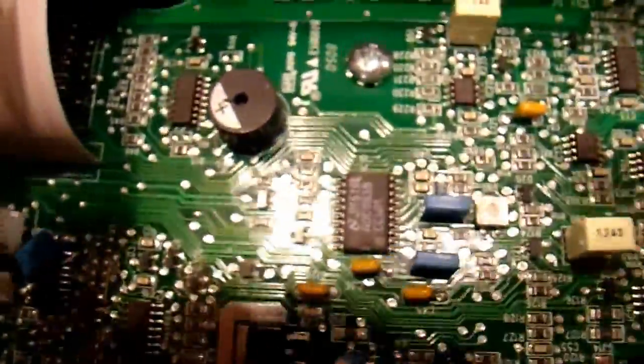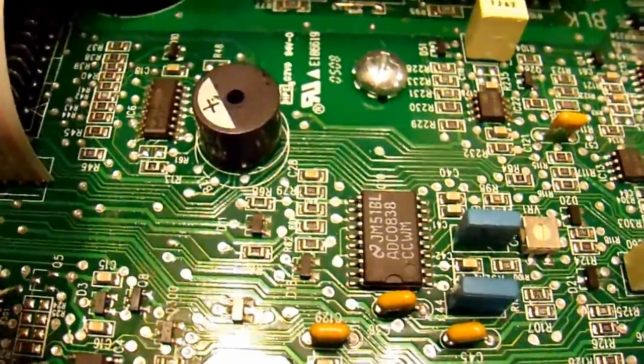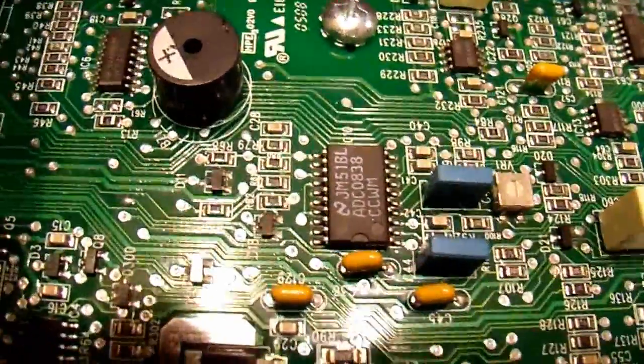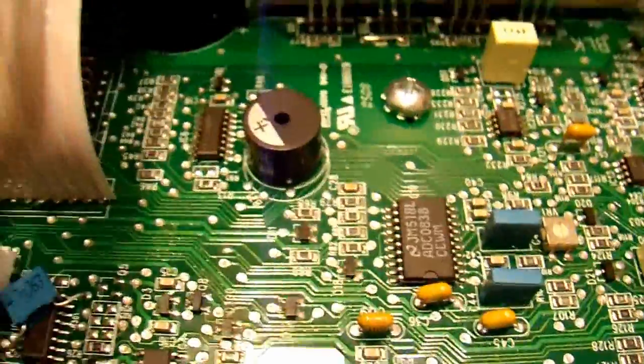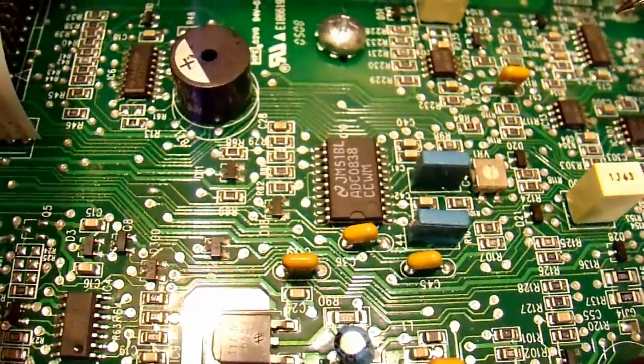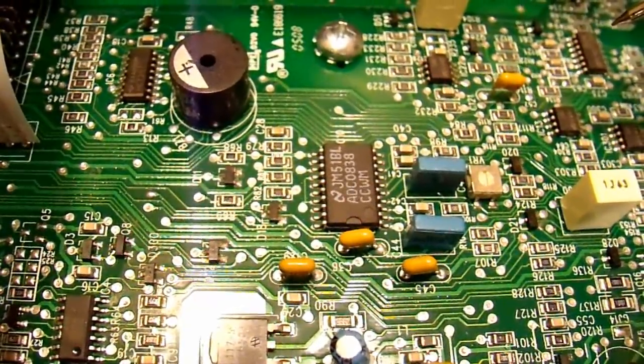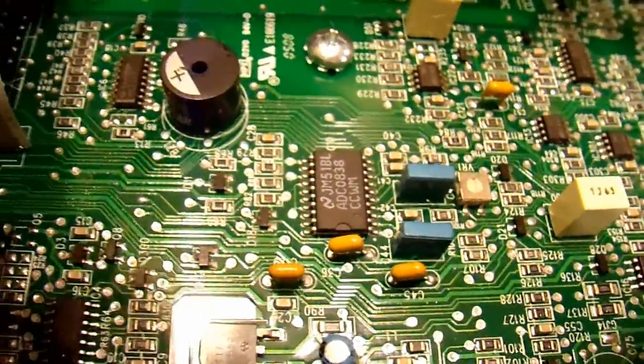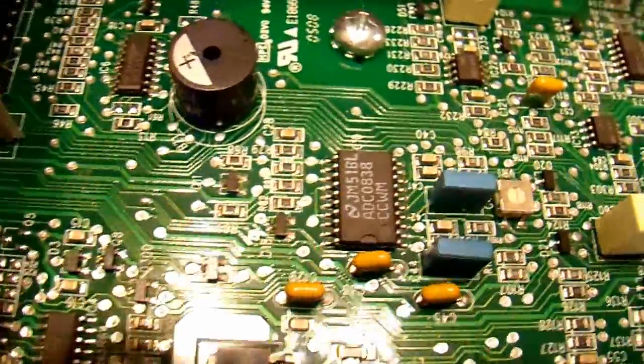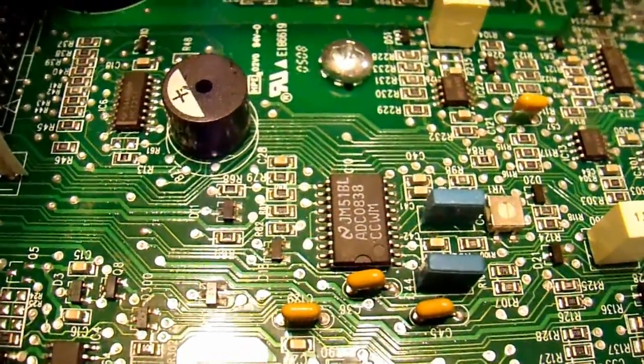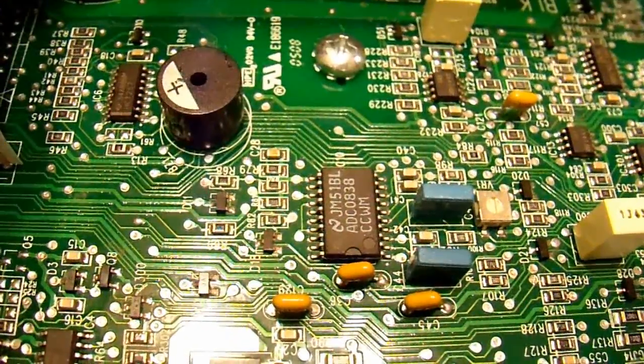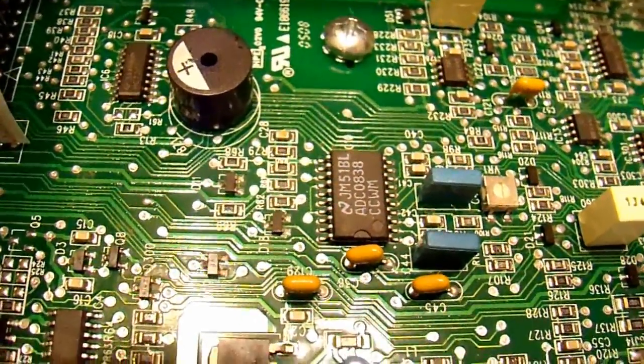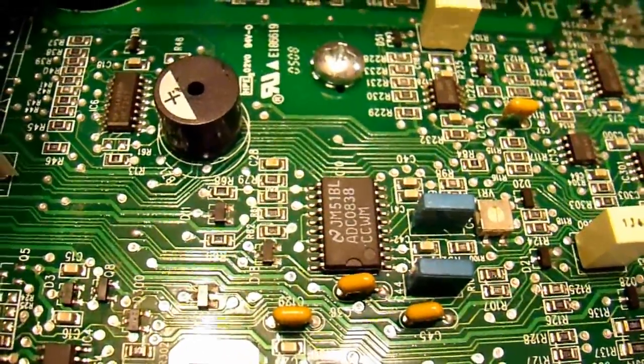Here is the slave UPS, just taking a top-down view of it. And I'll come in here on this particular portion of the board to show you what I mean. I looked into a number of different ways that I could potentially force this into inverter mode to prevent it from going into bypass mode, which would short-circuit my other UPS and potentially be catastrophic.